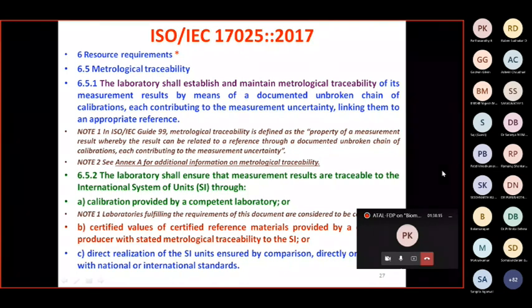So that is why the most convenient thing is to calibrate all your instruments and gauges, preferably with a NABL approved laboratory. This requires to be done only for instruments and gauges which require traceability to be maintained. As I said, for the water flow meter, you need not engage a NABL approved laboratory. Maybe for a thermometer measuring room temperature, you require to do that.